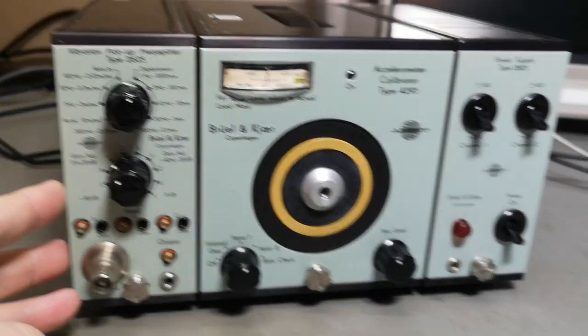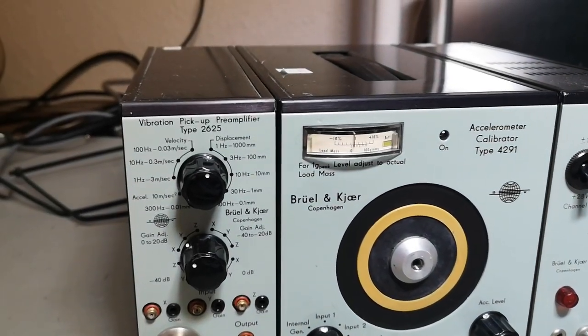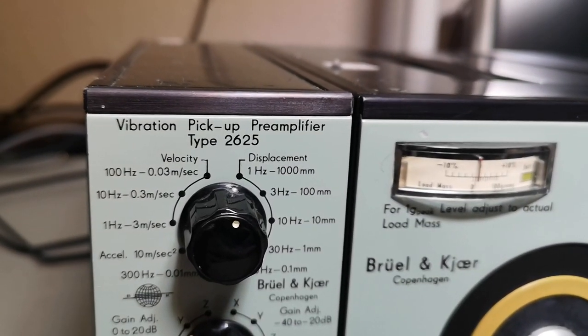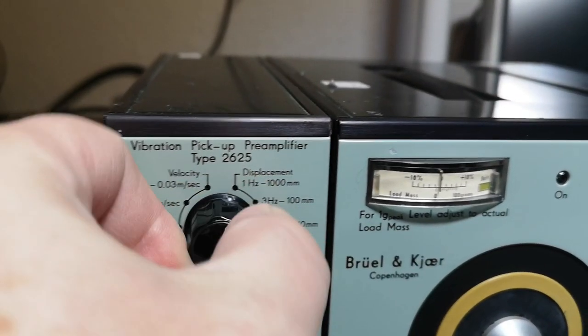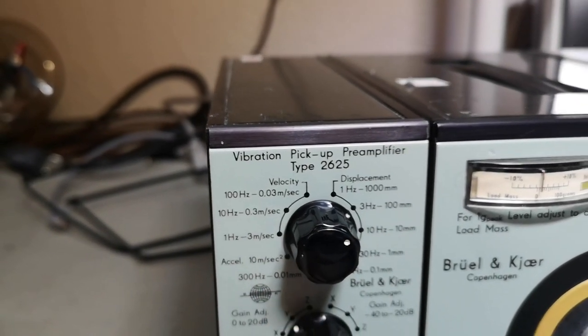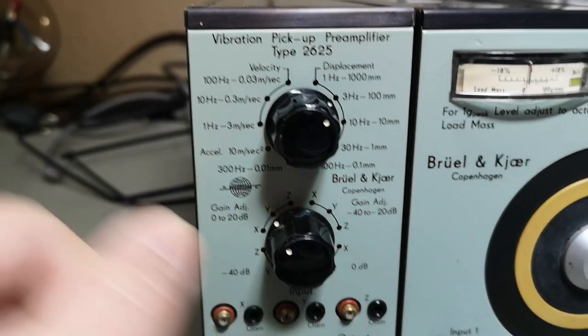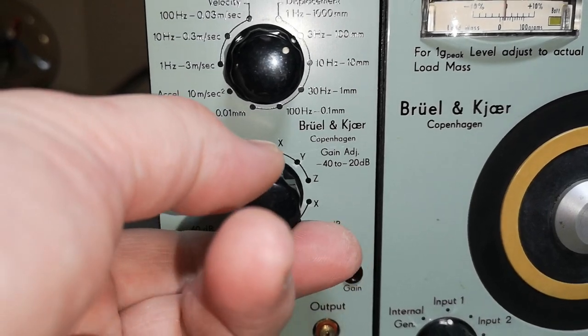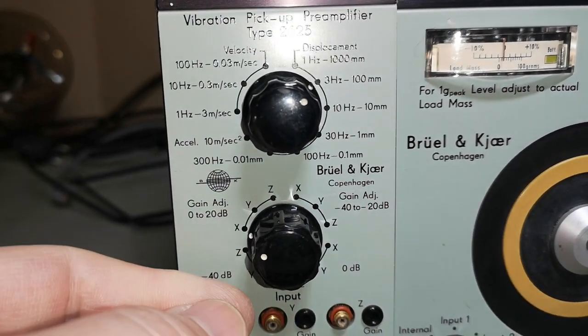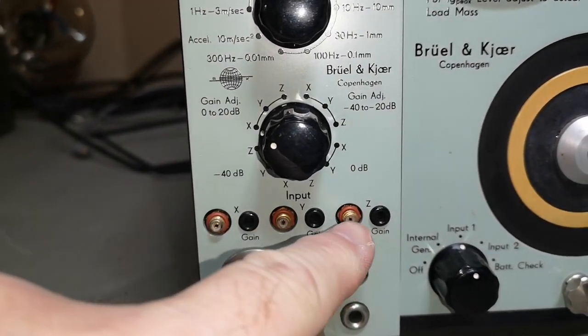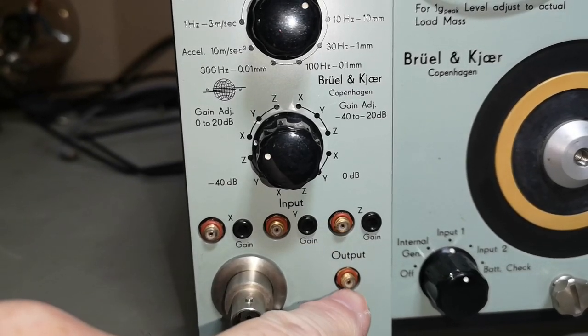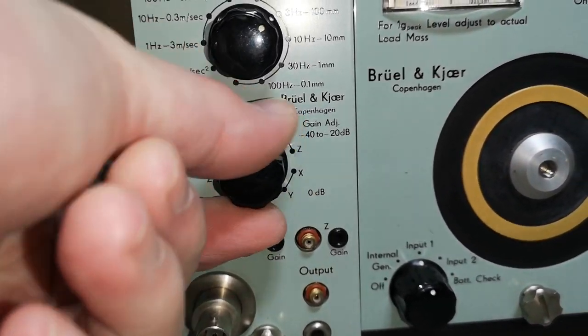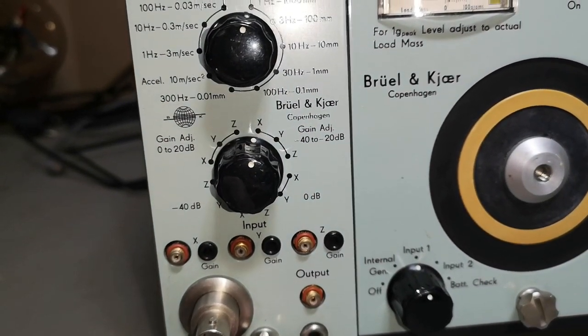As far as I can see, it contains a vibration pickup pre-amplifier type 2625, where you can select all sorts of different displacement and velocity and whatnot, and the different angles of gain and stuff like that. I guess you connect three different sensors and then you get the output. Here you can select between the different sensors and then you'll get the output.